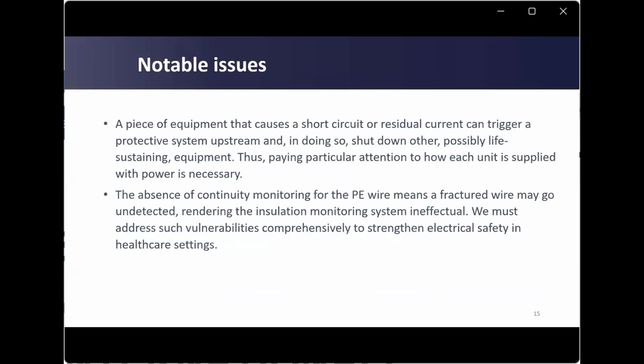Some notable issues. A piece of equipment that causes a short circuit or residual current can trigger a protective system upstream and, in doing so, shut down other, possibly life-sustaining equipment. Thus, paying particular attention to how each unit is supplied with power is necessary. The absence of continuity monitoring for the PE wire means that a fractured wire may go undetected, rendering the insulation monitoring system ineffectual. We must address such vulnerabilities comprehensively to strengthen electrical safety in healthcare settings.